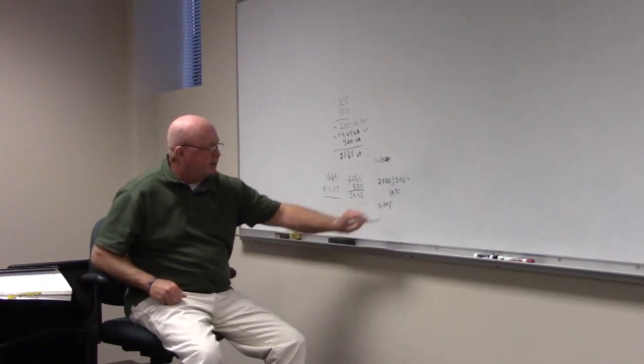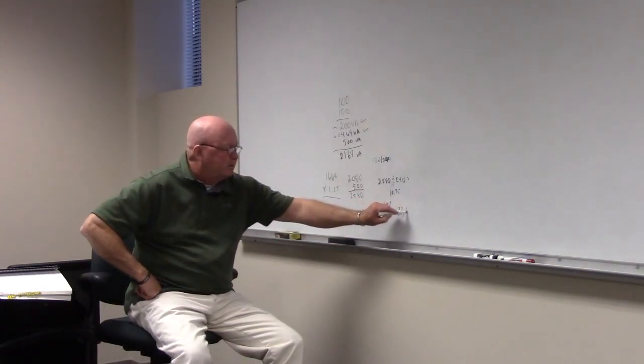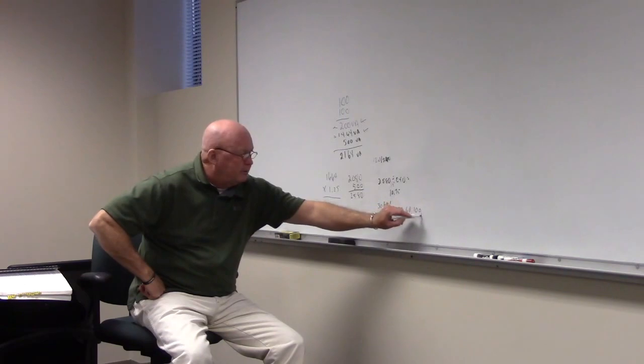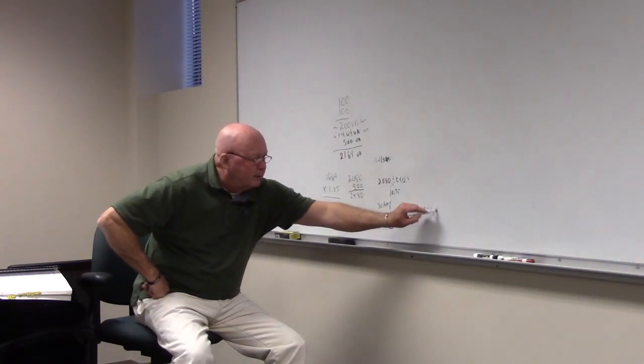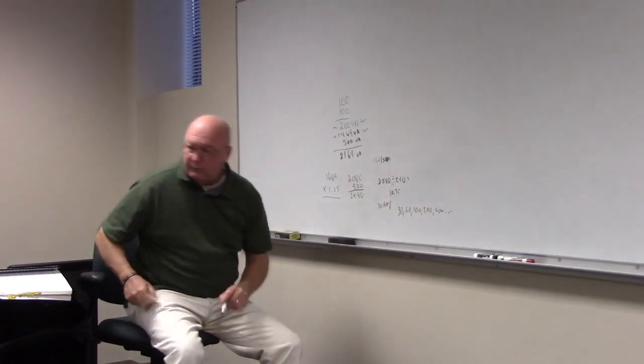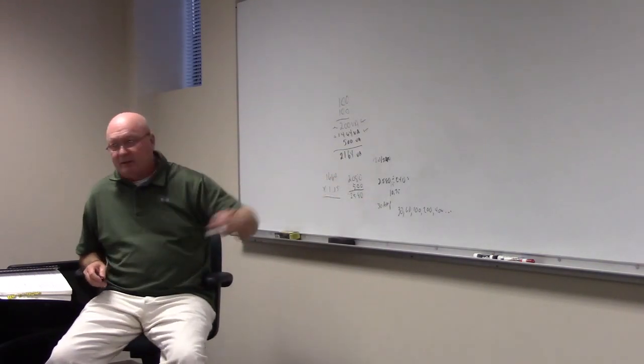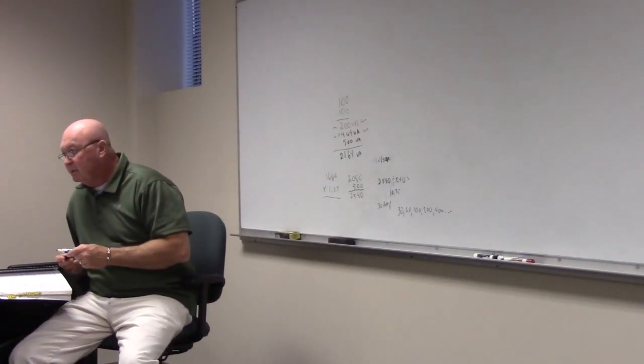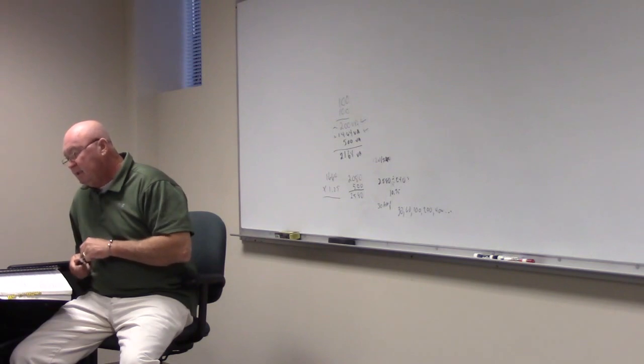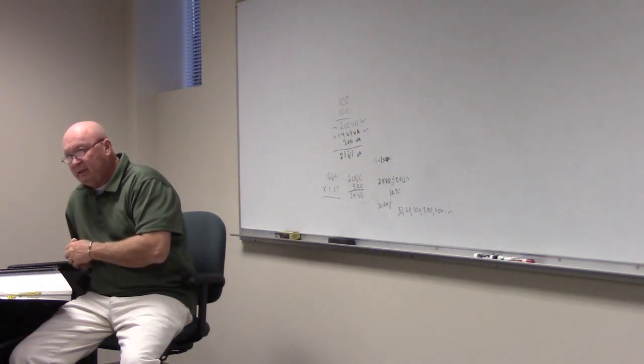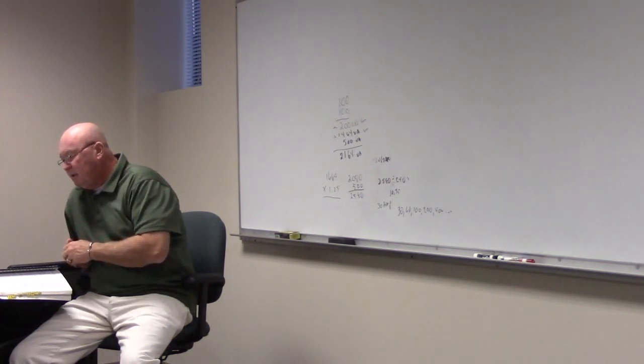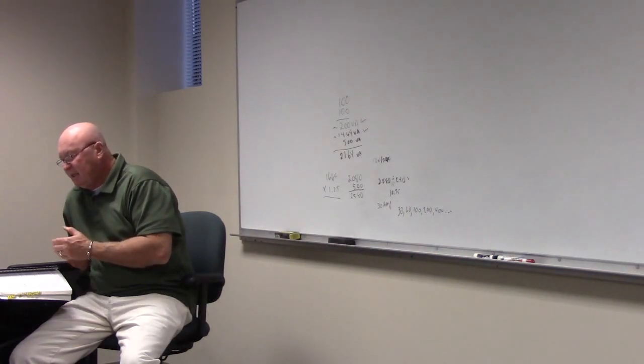Because when you buy a disconnect, they're either 30, 60, 100, or 200, or 400, and so on and so forth. But when you buy that disconnect, the smallest one you're going to be able to buy is 30 amp. And again, you may want to do it in aluminum. It says you can do it at number 8, whereas in copper we do it at number 10. It costs no more for number 10. I think I'd do it in copper, wouldn't y'all?